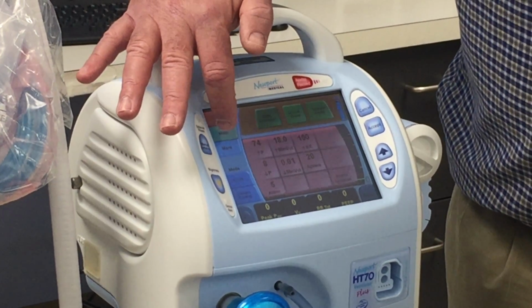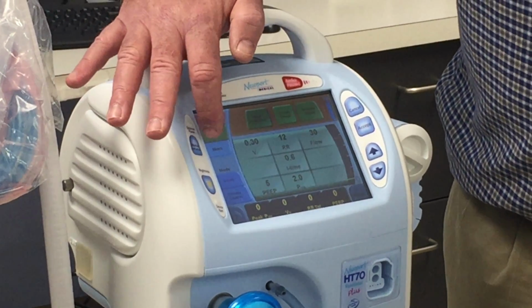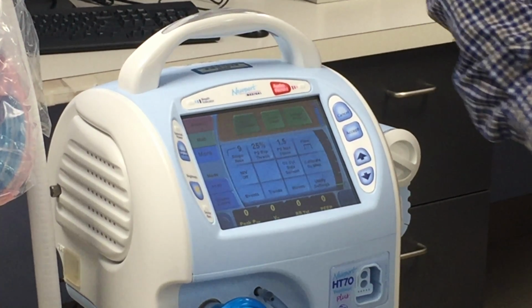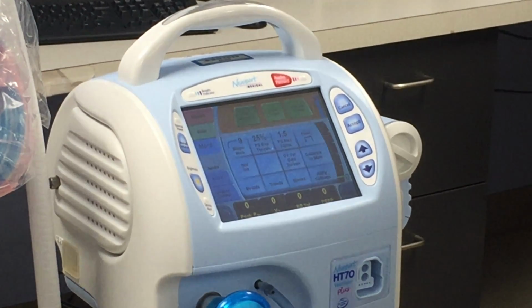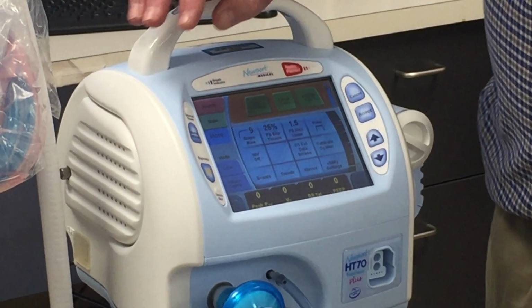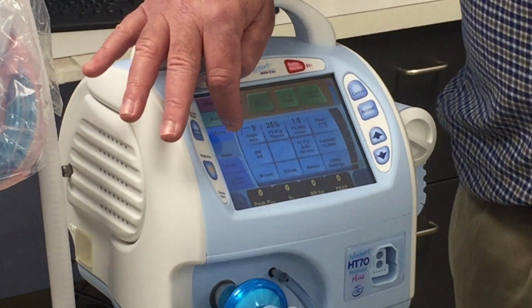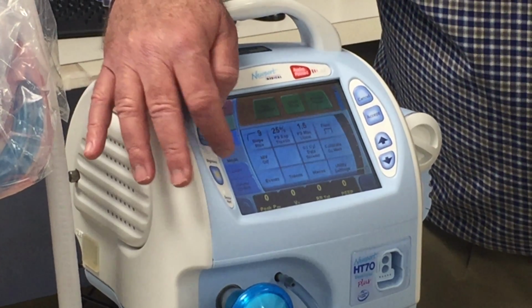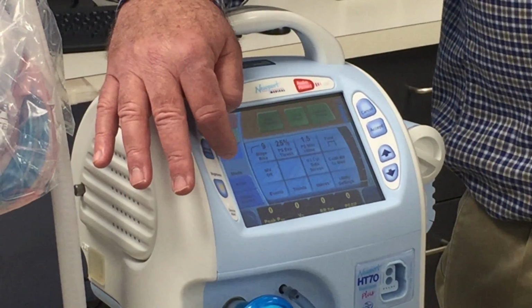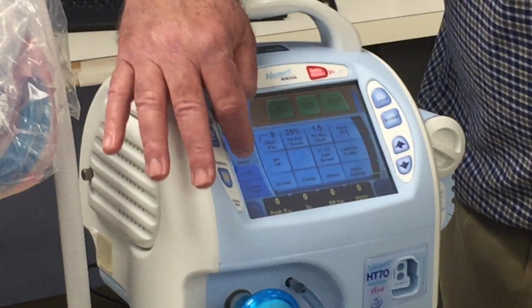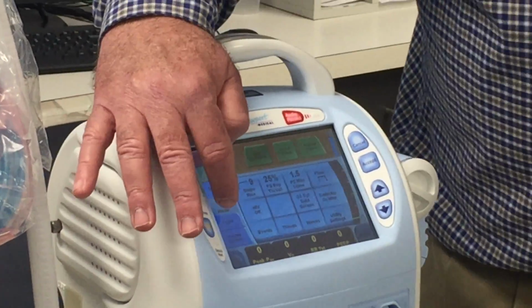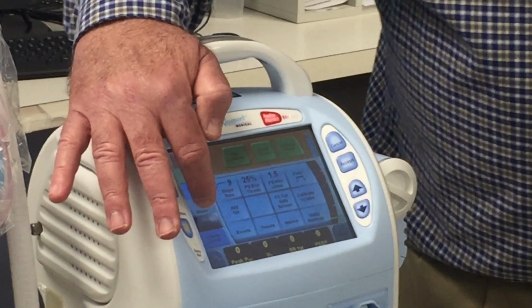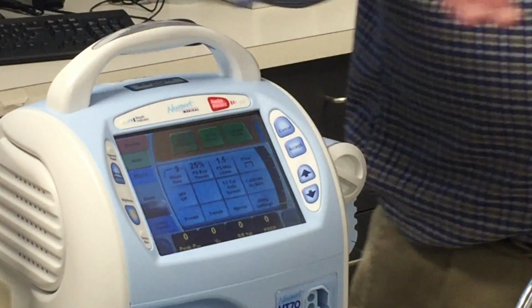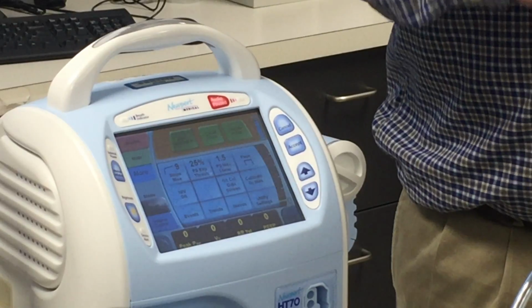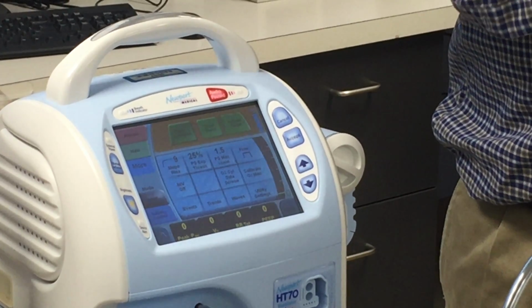You can see on the left side here we have alarms, we have our main menu, and our more screen, which is kind of blue, and those are some patient comfort settings that I'll go through. And then below that you can see we have mode. So right now we're in volume control and we're in assist control. If I want to change that, the options we have are assist control, SIMV, or spontaneous. With spontaneous, we can get pressure support, CPAP, or we can do non-invasive.